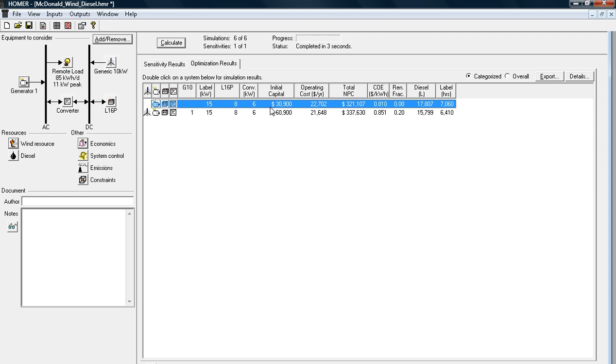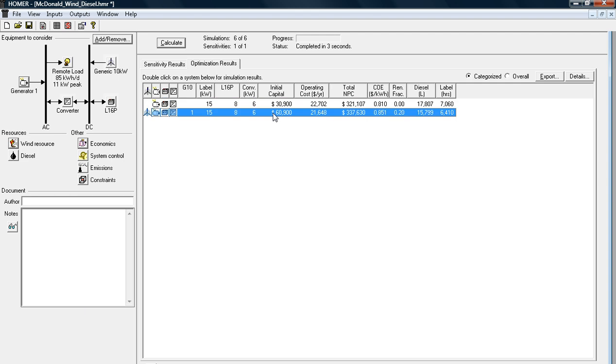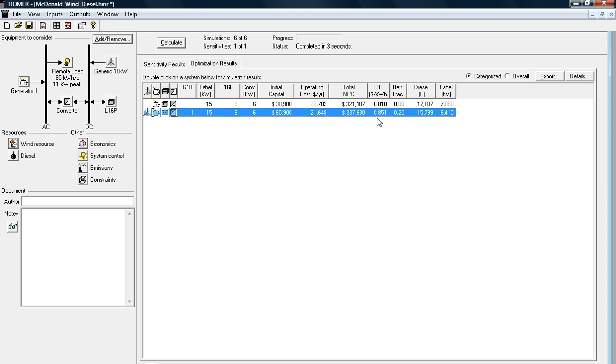However, that's because the initial capital cost is so much lower. I'm prepared to spend that initial capital, though, because I'm really interested in putting in a wind turbine. So if I look at this system here, it shows me that my operating costs are actually a little bit lower at $21,000 per year, which is offset by that renewable energy that I'm producing. My total net present cost of the system is going to be about $337,630. My cost of energy is going to be roughly $0.85 a kilowatt hour.